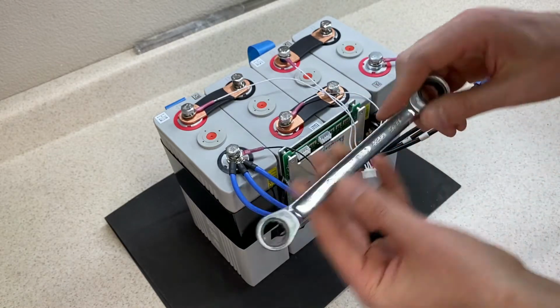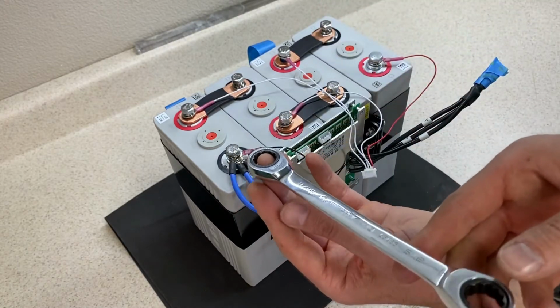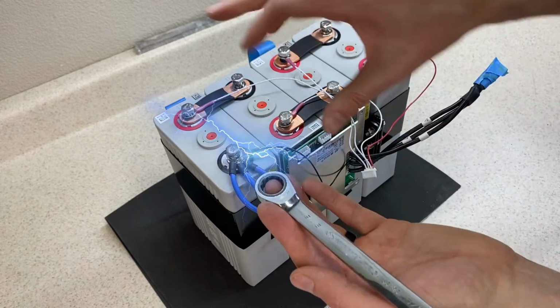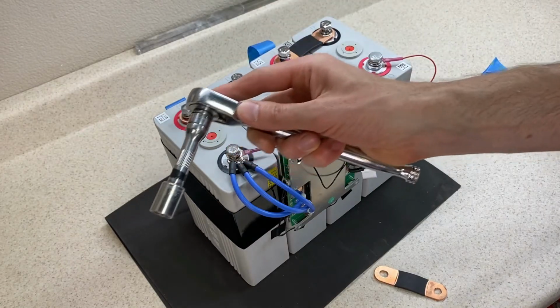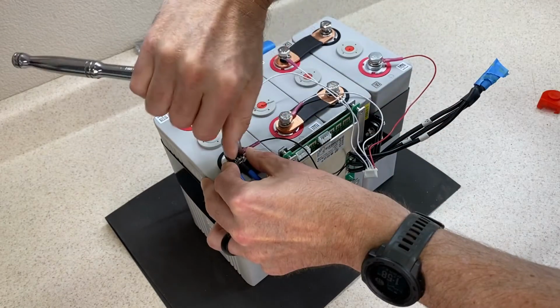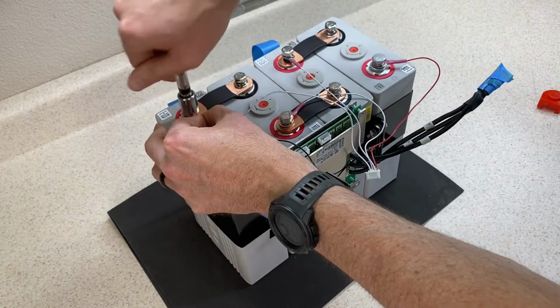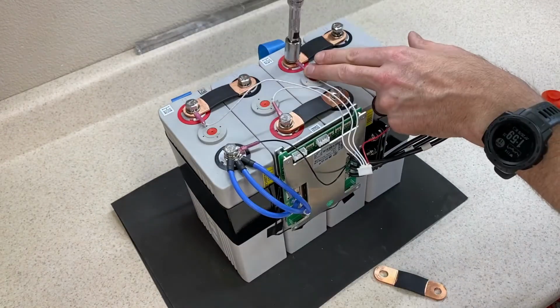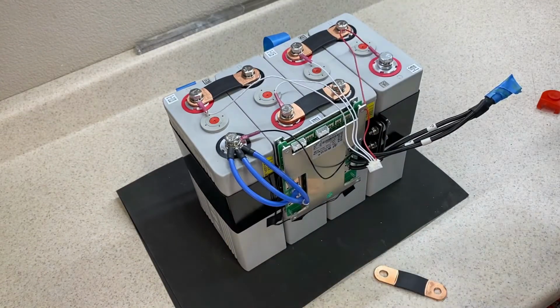When tightening these bolts though, do not use something like this. This wrench could swing around and cause a short between the 2 terminals while you're tightening the bolts. I always use a ratchet with an extension and possibly even a deep socket. You could also put electrical tape or even a length of heat shrink tubing around the handle for extra safety.